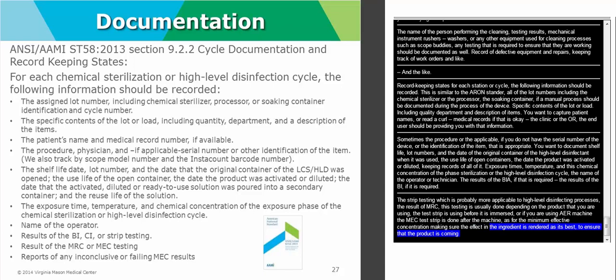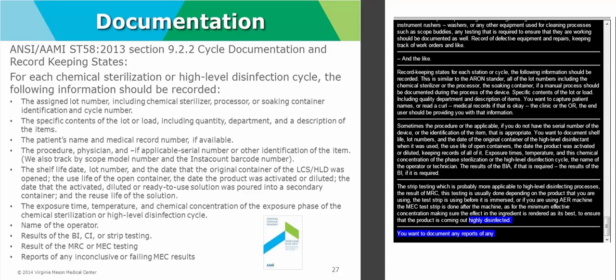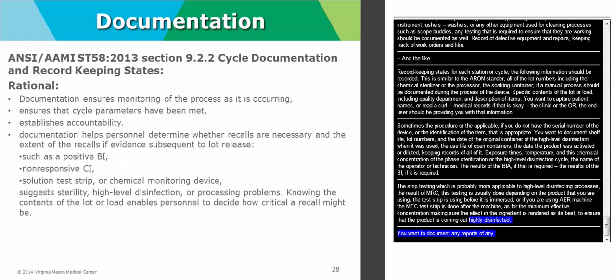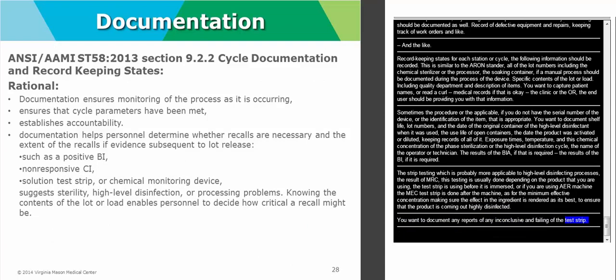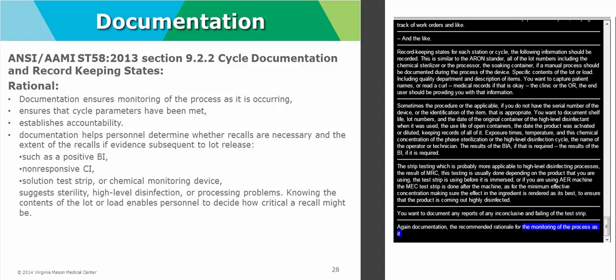And then you want to document, of course, any reports of inconclusive or failing MEC results, a failed test strip. And again, the rationale for documentation is that it ensures the monitoring of the process as it's occurring, ensures that cycle parameters have been met in order to be able to release those products to sterile storage or render them safe for patient use.